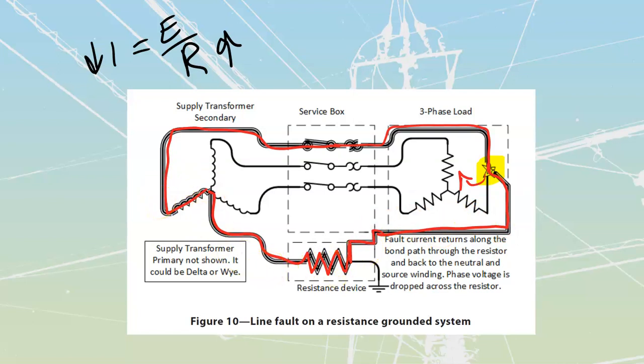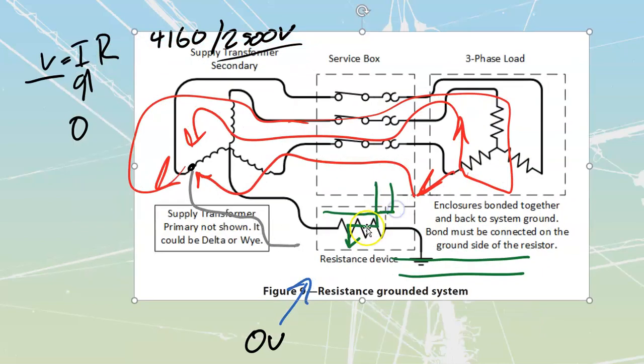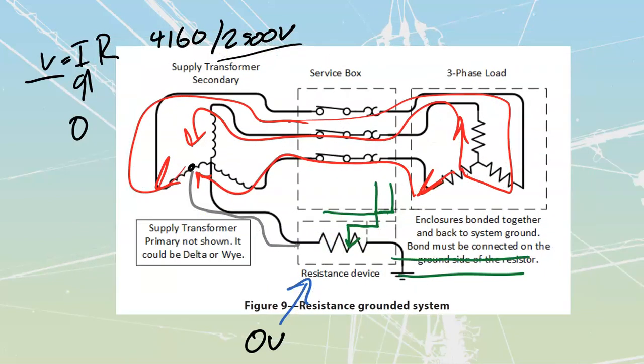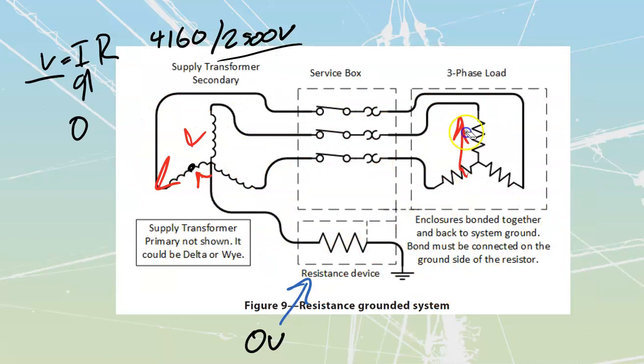Remember how I said it would be really dangerous if we connected our bond path on the wrong side? Let's trace through what would happen if I did so. Let me erase all of these here. Okay, what I'm going to show you over here is going to be wrong—we don't want to do this. So instead of having that there, we've taken our bond and connected it on this side, on the neutral side of our resistance device. And if we go to a fault in the same spot, we'll put a fault right over there.